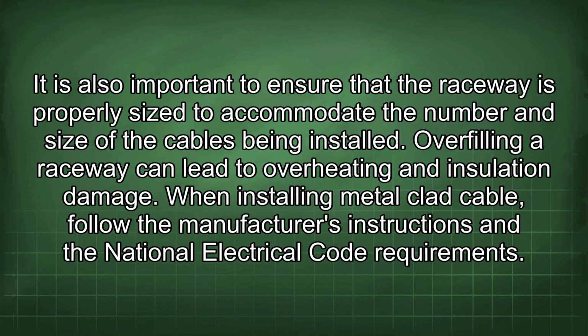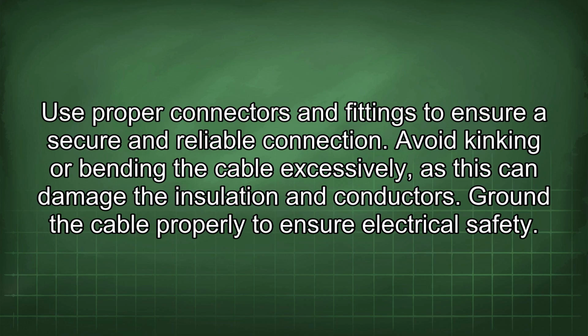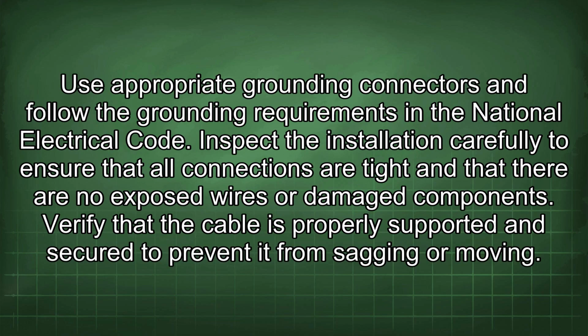When installing metal-clad cable, follow the manufacturer's instructions and the National Electrical Code requirements. Use proper connectors and fittings to ensure a secure and reliable connection. Avoid kinking or bending the cable excessively, as this can damage the insulation and conductors. Ground the cable properly to ensure electrical safety. Use appropriate grounding connectors and follow the grounding requirements in the National Electrical Code.